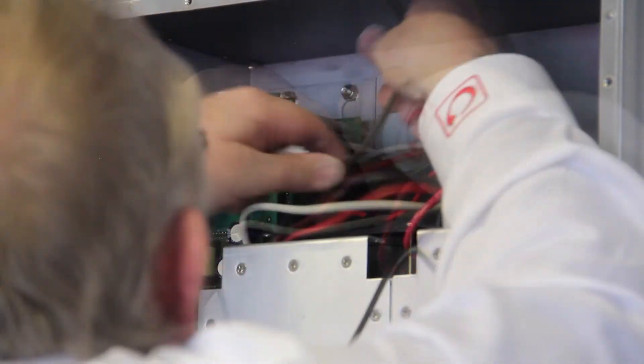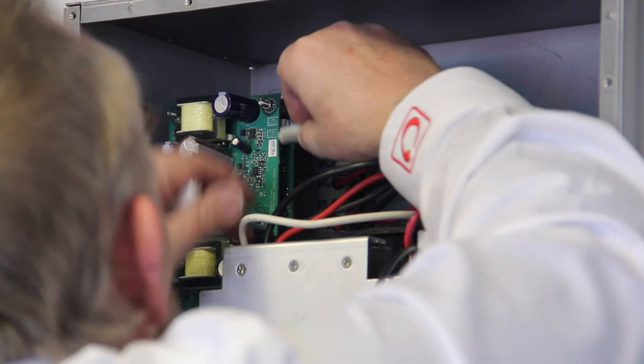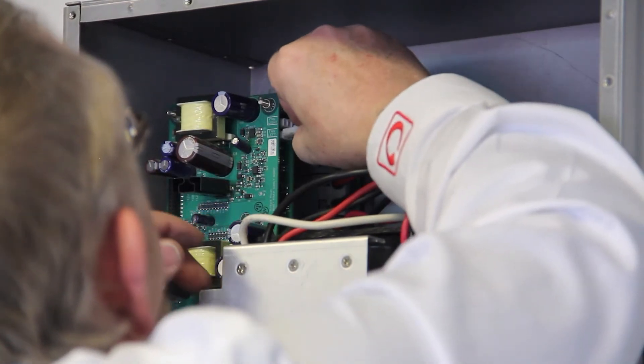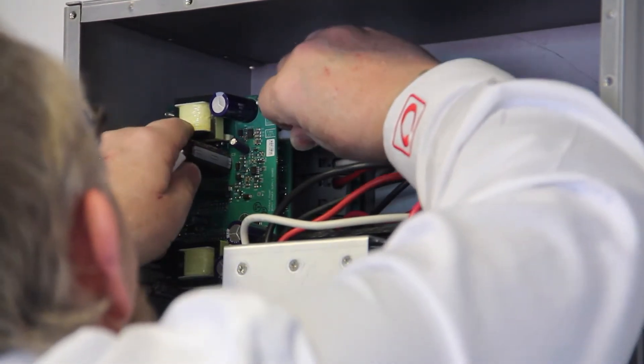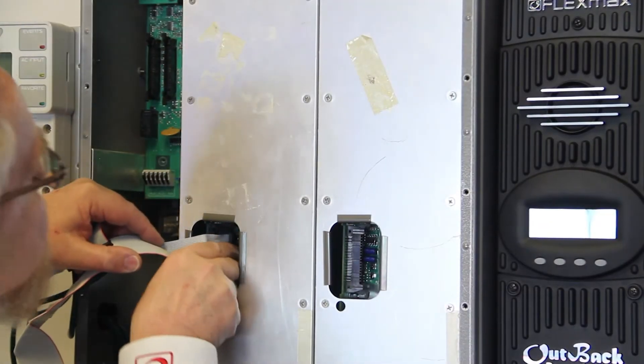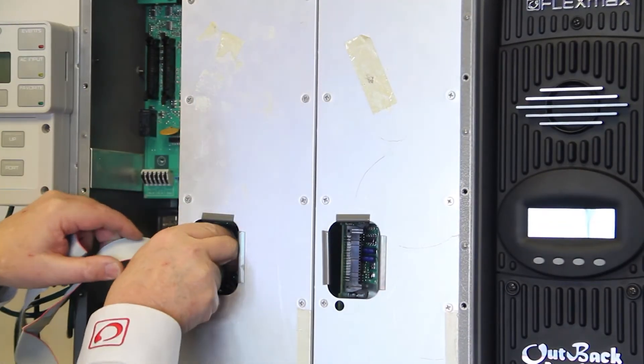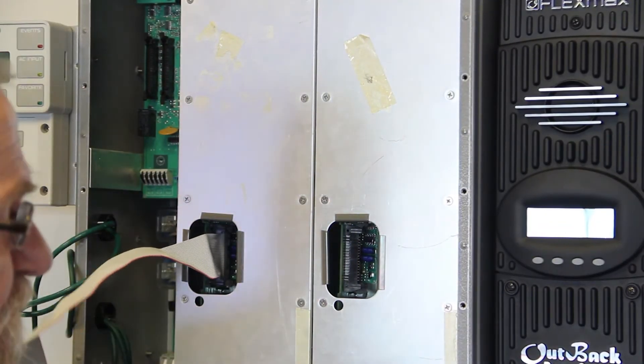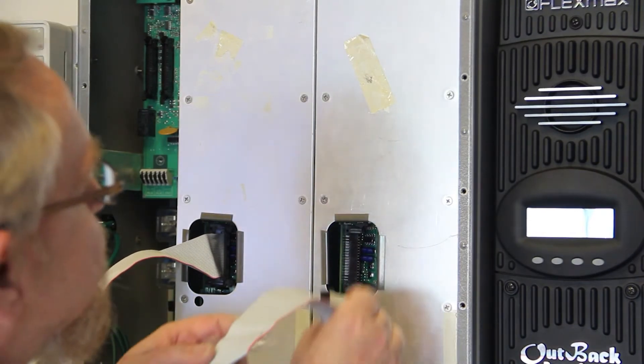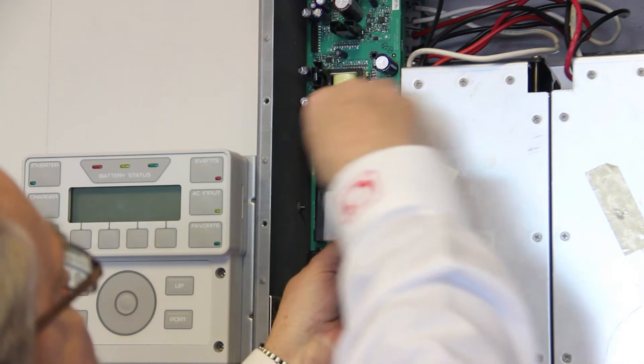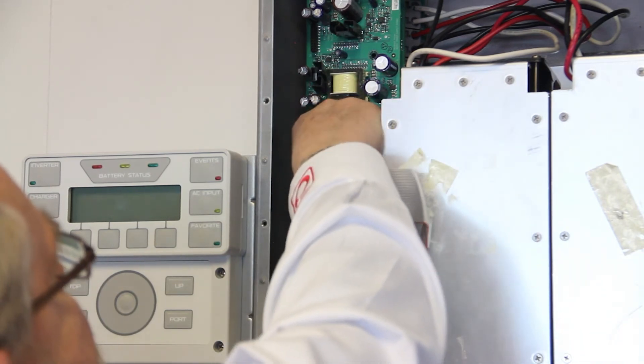Connect the two fan wires back to the control stack. Connect one end of the ribbon cable to each power module and the other end to the proper control stack slot. Left module connects to the right slot while the right module connects to the left slot.